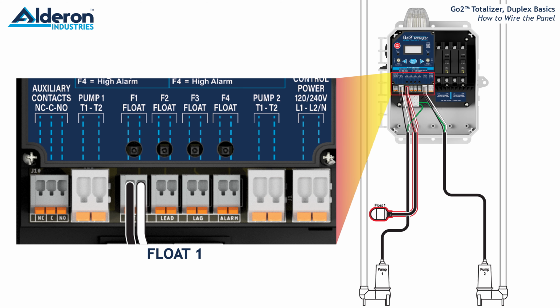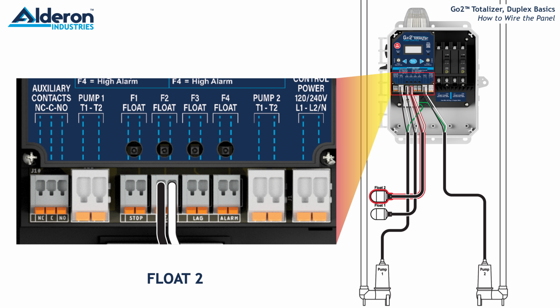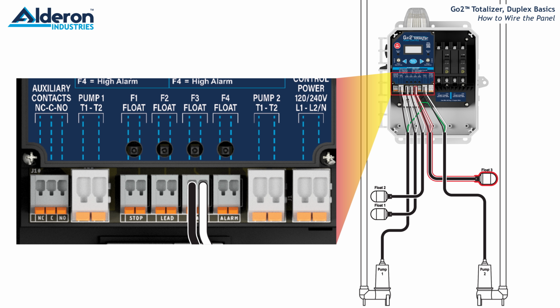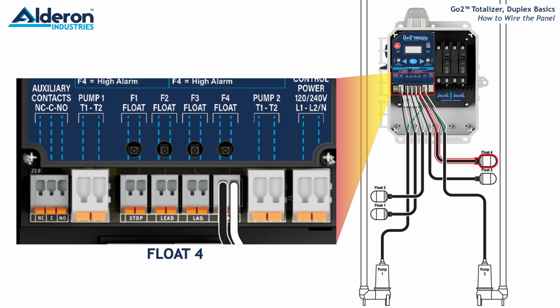Install float 1 in the F1 float position. This will be the stop pump or low-level or redundant off float. Install float 2 in the F2 float position. This will be the lead float or timer enable float. Install float 3 in the F3 float position. This will be the lag float or the peak timer enable float. Install float 4 in the F4 float position. This will be the high alarm float. Note, if installing fewer than 4 floats, the float positions in the tank must remain in the same order.